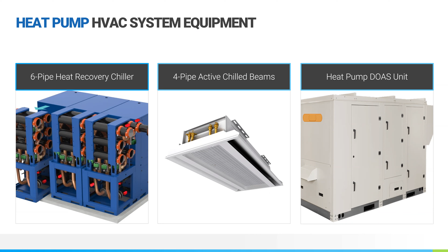These systems didn't change overall. It was still a heat pump HVAC system no matter which route they went. They were just changing what would provide the hot or warm source of heat, or the heat rejection to that heat recovery chiller. So it came down to either boiler towers, a ground source system, or a wastewater heat recovery system. They weighed all three options.